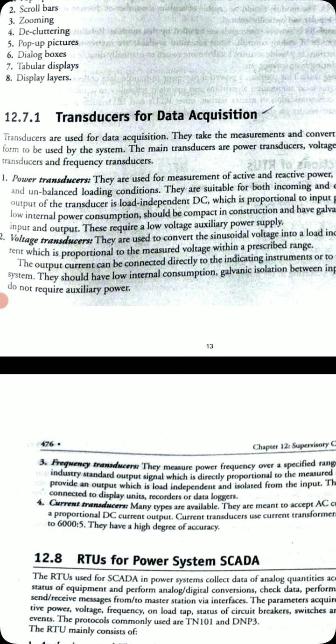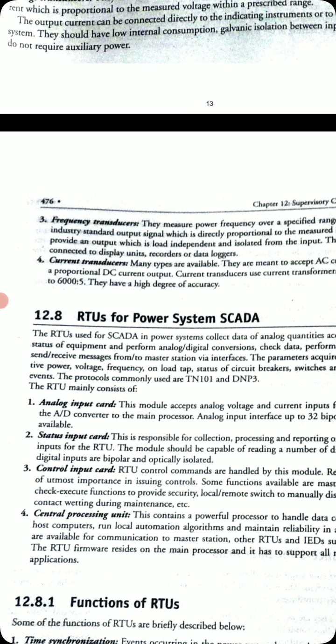Coming to the RTUs for the power system SCADA. What is an RTU, the remote terminal unit, consisting of, or what are the different things in the RTU? The RTU has an analog input card. This module accepts analog voltage and current inputs for transmission through an analog to digital converter to the main processor. An analog input interface of up to 32 bipolar and unipolar inputs is available.